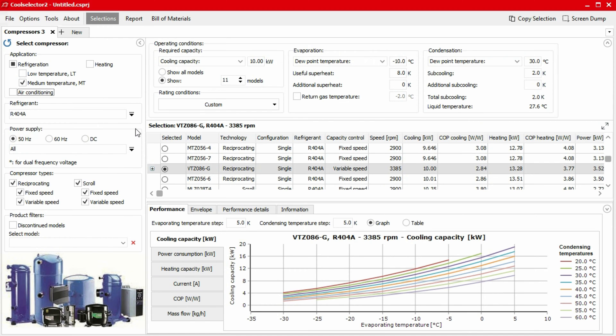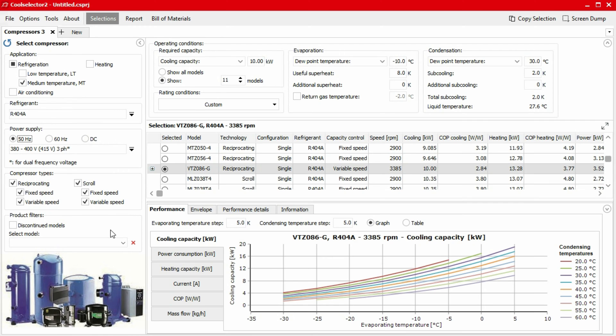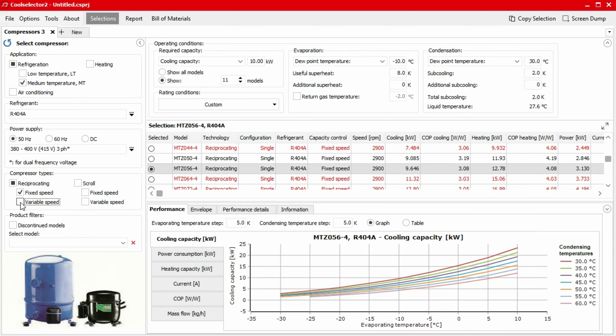Then we specify the power supply to the compressor. In our application, we'll be connecting to a 50 hertz, three phase, 415 volt power supply. So we select these from the options. Now we can choose which type of compressor we would like to use. For this example, we require a fixed speed reciprocating compressor. So we unselect the other options.